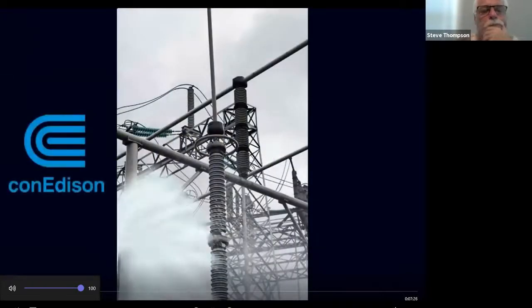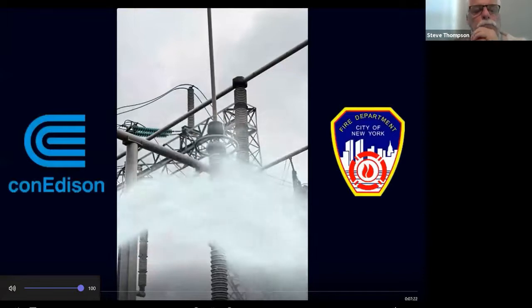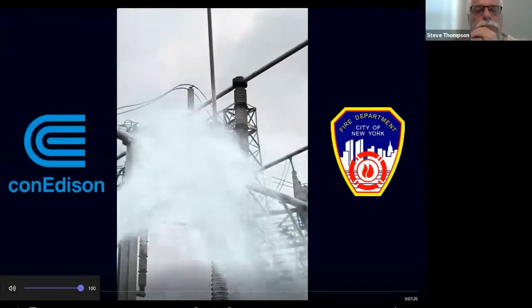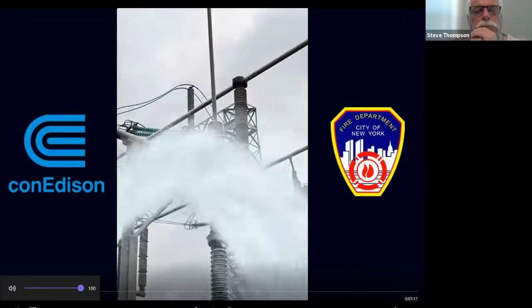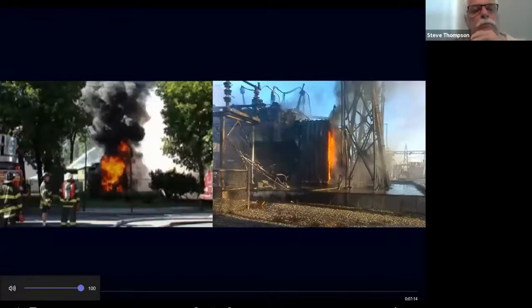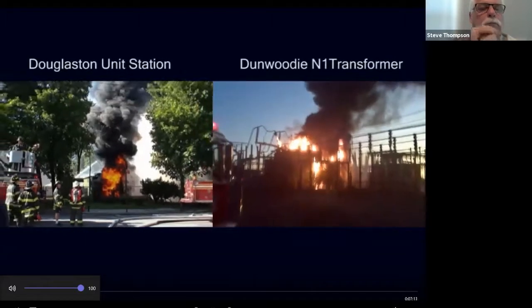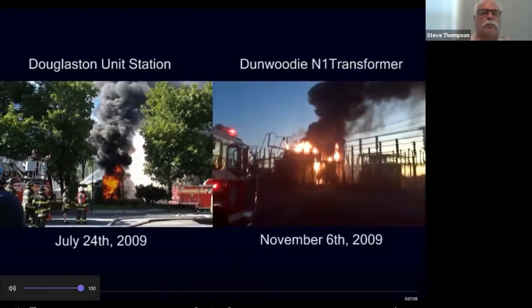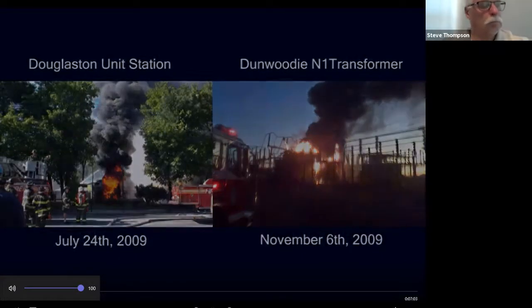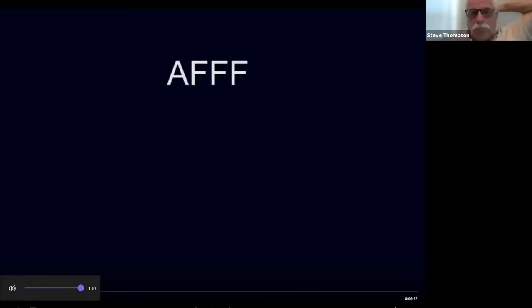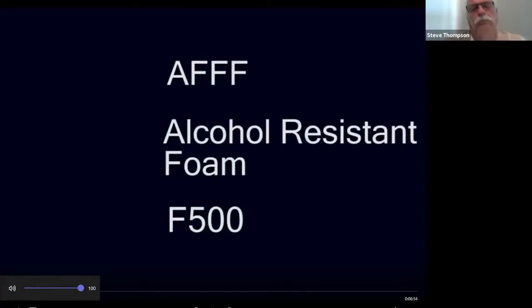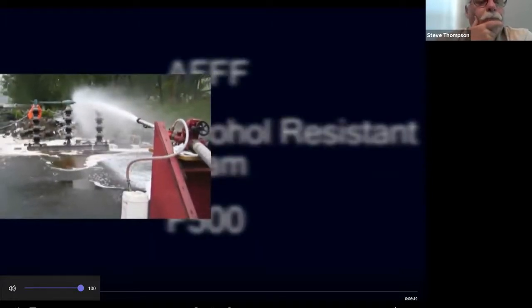In 2006, we began a joint venture with the FDNY to prove that water could be safely used in a high voltage environment to extinguish or protect equipment impinged by fire. 2 recent incidents caused us to rethink our response posture. We realized that we needed to look for a product that will allow us to knock the fire down quickly without compromising the safety of first responders. Along with the FDNY, we looked at the products available on the market and chose 3: AFFF, alcohol-resistant foam, and F500 encapsulating agent. Preliminary testing was conducted at the Fire Academy using a disconnect switch energized to 50,000 volts.